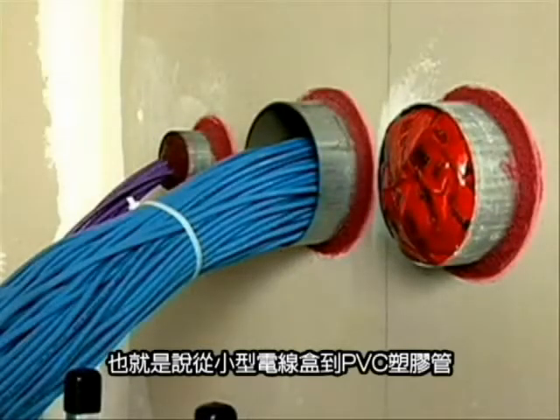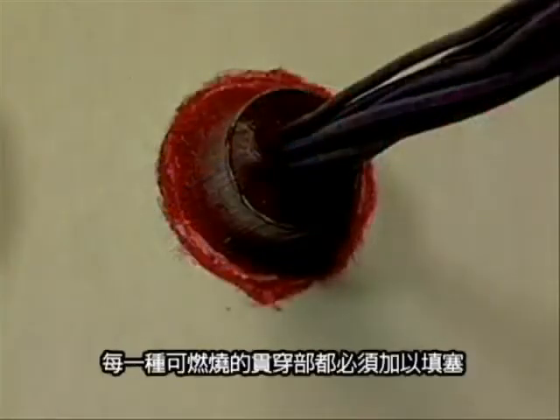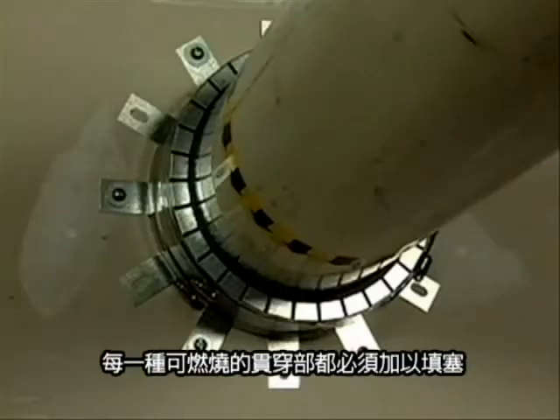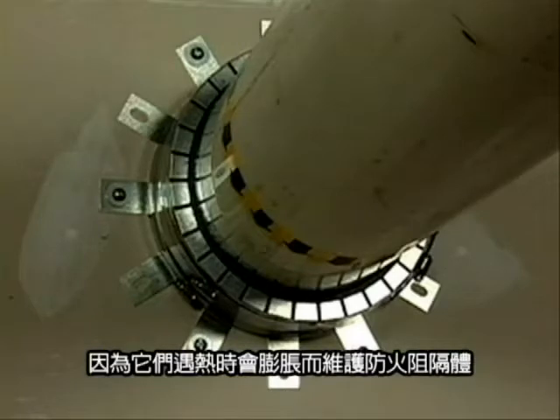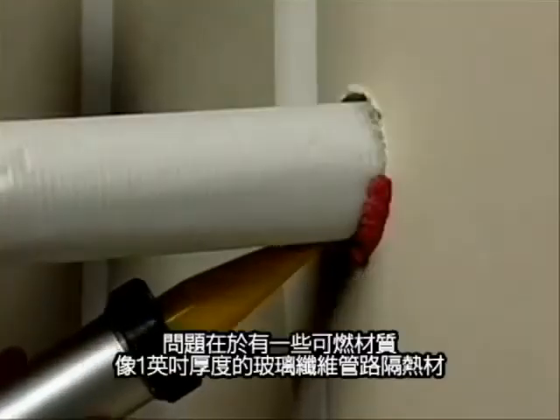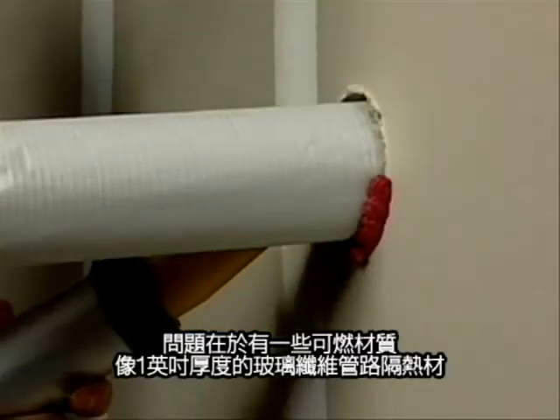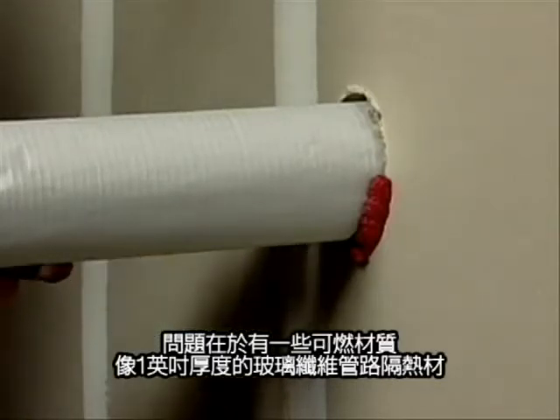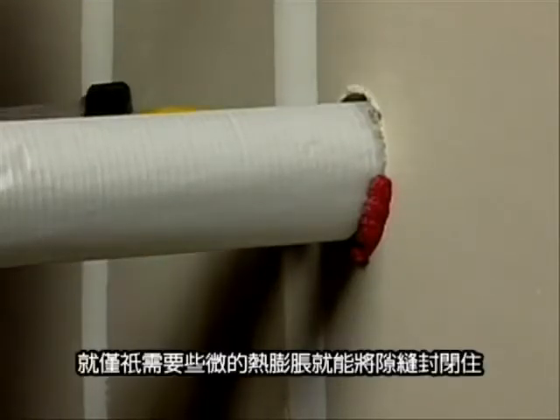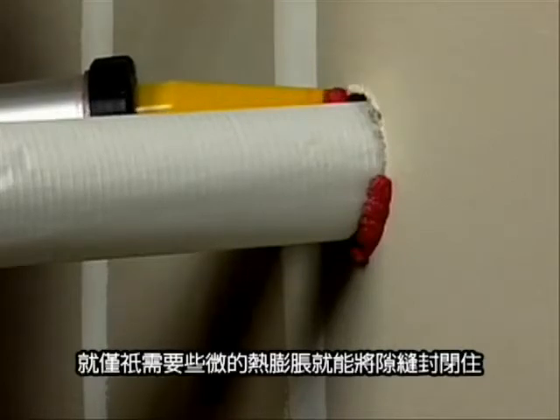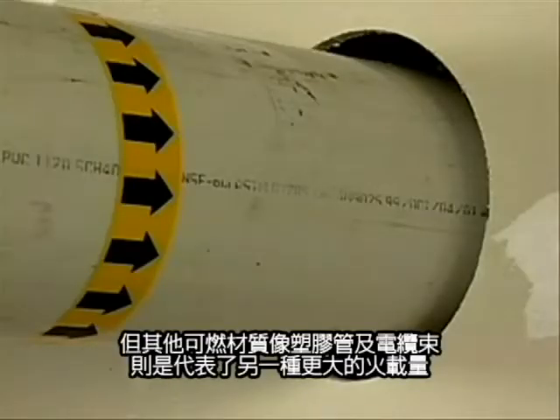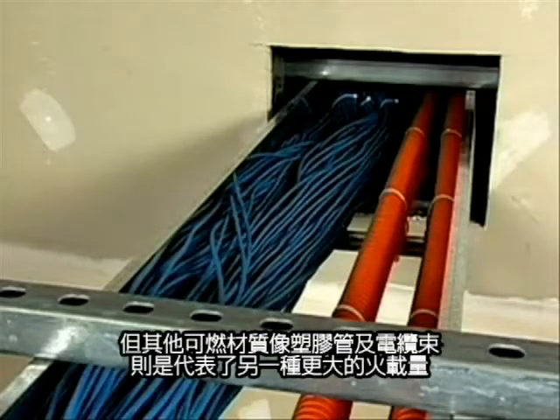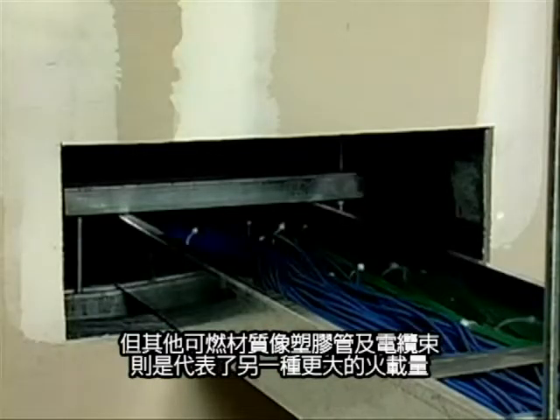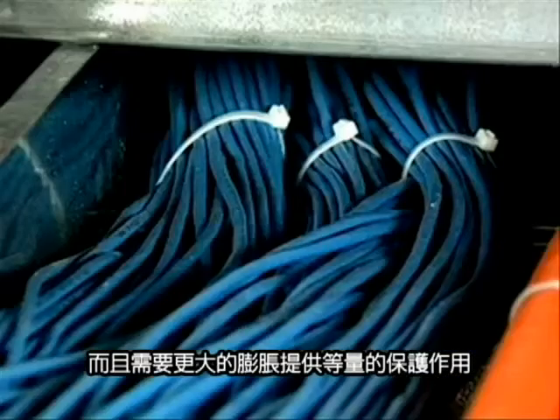This means that every combustible penetration, from the jacketing on a small wire to a large diameter PVC pipe, must be filled in as it melts in order to preserve the fire barrier. The problem is that some combustibles, like 1-inch thick fiberglass pipe insulation, require very little intumescent expansion to adequately close the void, while others, like plastic pipe and cable bundles, represent a far greater fuel load and generally require more expansion to provide the same amount of protection.